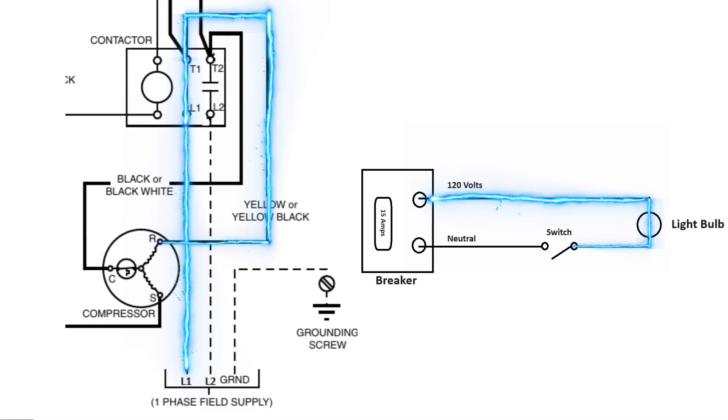But carrying on, we see as we trace the common line, we go all the way back to T2 on the top side of the contactor. And as we continue, what do we come to? We come to an open switch. We have an open drawbridge. And this is why our compressor is not running.